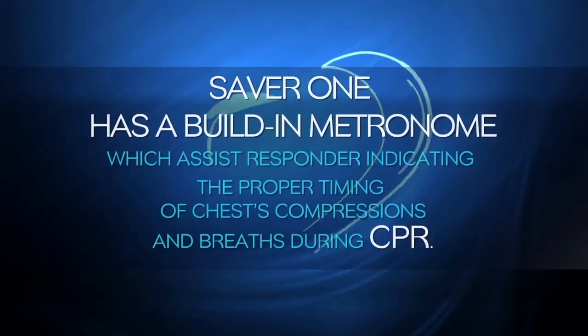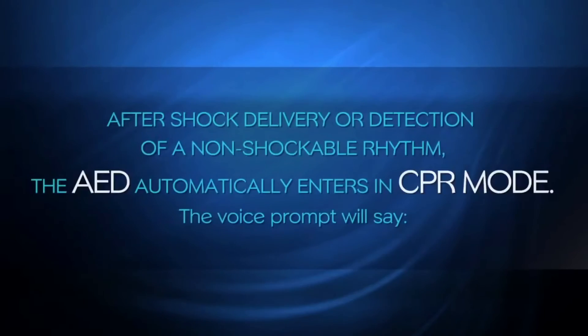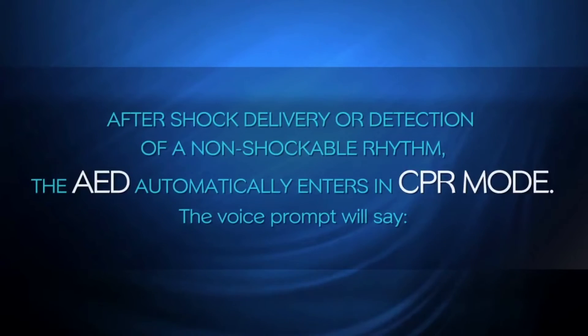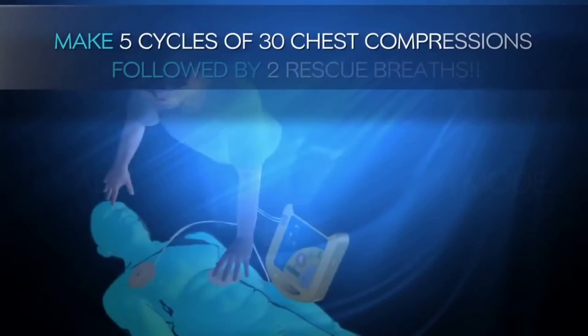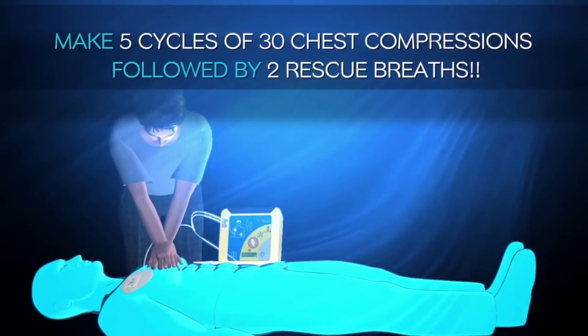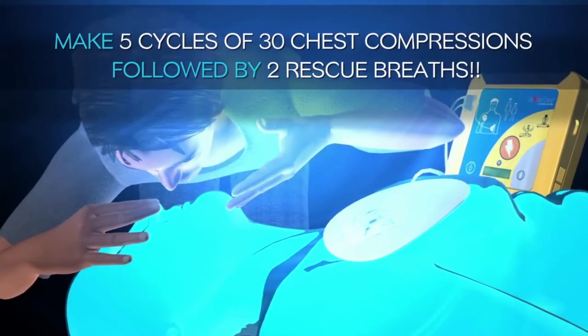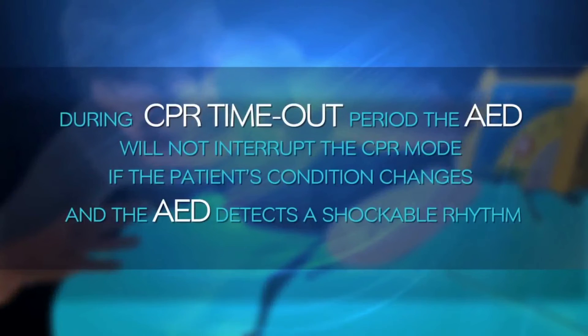In CPR mode, SAVER ONE has a built-in metronome which assists the responder by indicating the proper timing of chest compressions and breaths during CPR. After shock delivery or detection of a non-shockable rhythm, the AED automatically enters CPR mode. The voice prompt will say: 'It is safe to touch the patient. Begin cardiopulmonary resuscitation now. Make five cycles of 30 chest compressions followed by two breaths.' During the CPR timeout period, the AED will not interrupt CPR mode.